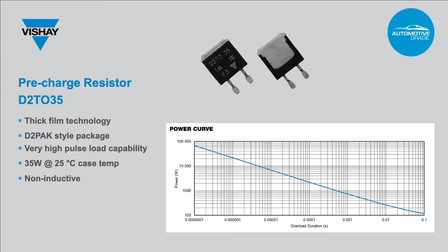In this case, a 3.3 K value was selected for the 250 millisecond pulse, which is safely within the capabilities of the power curve shown here and in the datasheet when extrapolated out to the required time.